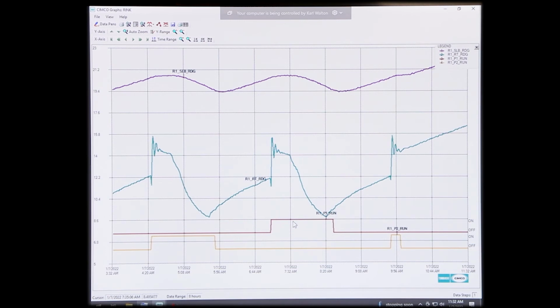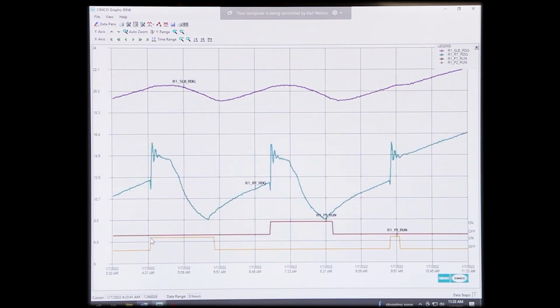Then we have P1 and P2 cold pump run. Now this is an interesting thing to check how long you're actually running this system and how you can try to save yourself some money and just update it. That's why I shifted. So if I go here, this is P2 down here. So P2, remember I said we cycle each pump every start. So if I go here, hold my mouse there and I look at the time, it says 5:49 a.m., right? So if I take that time there to this time here, 7:04. So now that tells me that basically an hour and 10 minutes, give or take, of off time that you have.